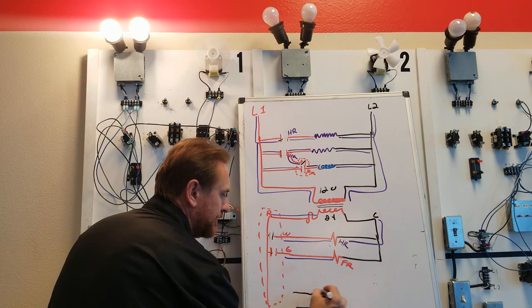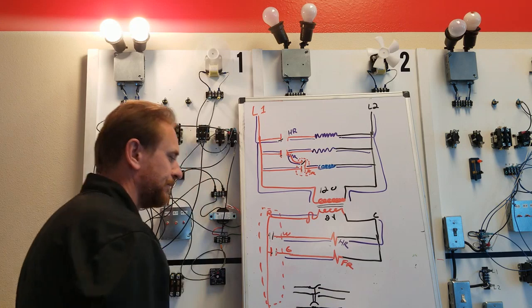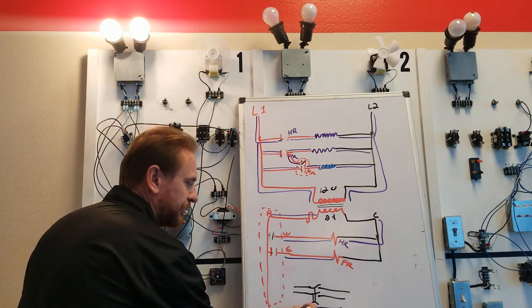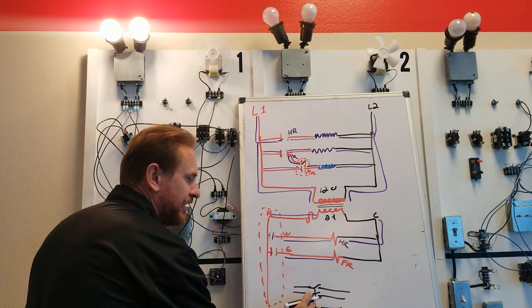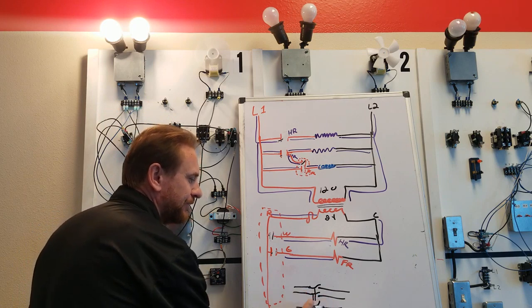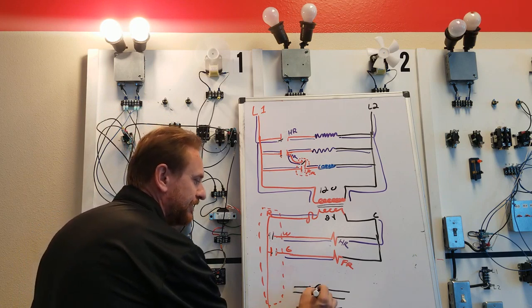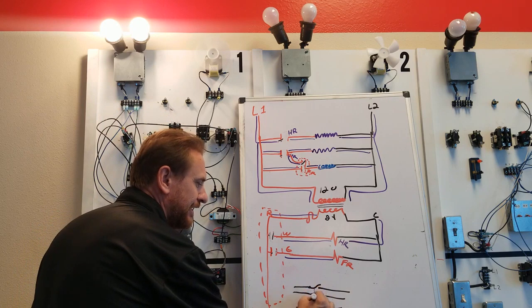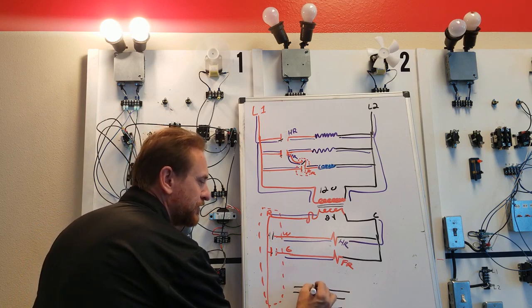Keeps one switch open. And then we have our second switch. It's also open. So when this heater, 24 volts, here's our W and C, gets hot, this bimetal pops down like this, which causes these rods to drop down, which causes this switch to drop down and close, this switch to drop down and close.